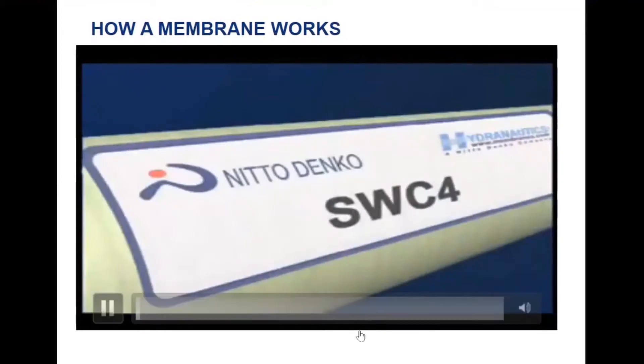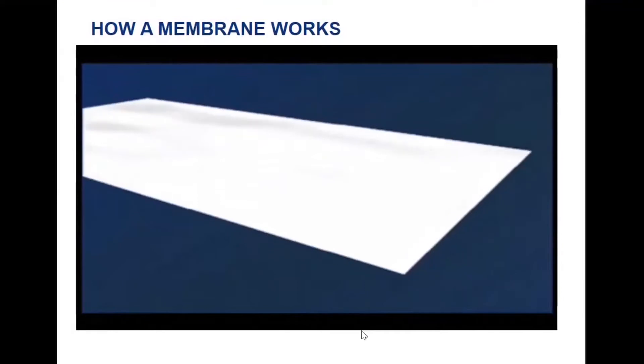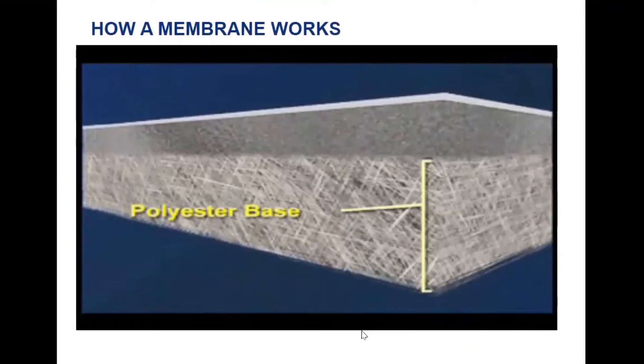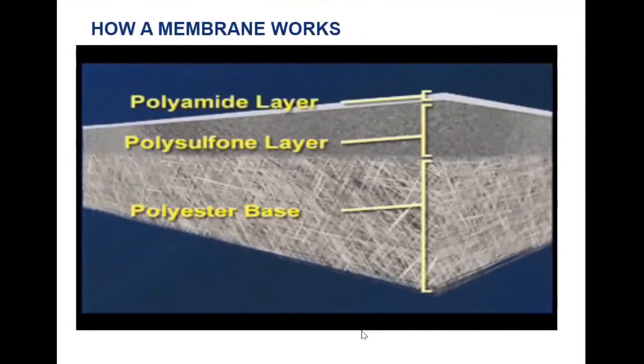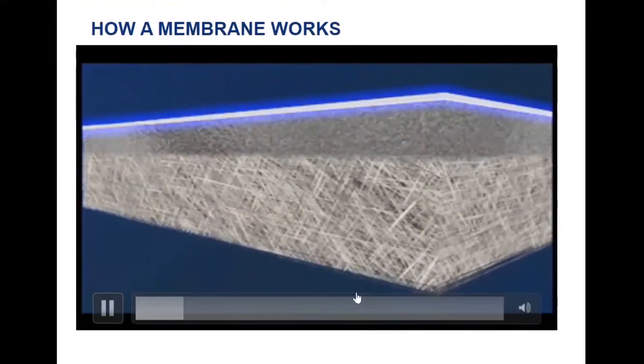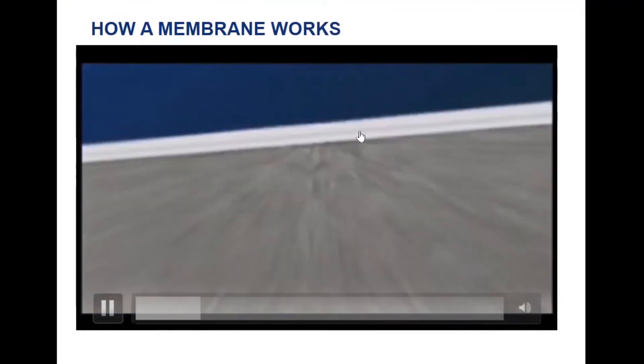To create our standard spiral wound membranes, we construct the flat sheet membrane using Hydranautics' automated casting equipment. We begin the process with a fabric support base and then coat it with a microporous polysulfone layer. This provides additional support for the top 0.2-micron thick membrane barrier layer. This top barrier layer makes the actual separation to purify the water. The semi-permeable polyamide layer consists of a thin film of polymeric material, a few thousand angstroms thick, formed on porous supporting material.